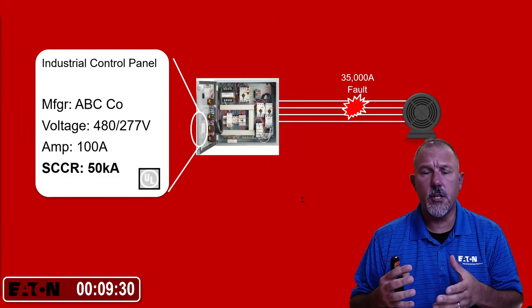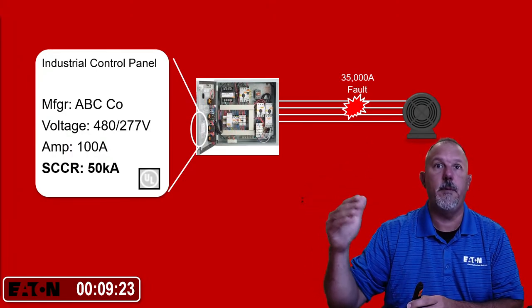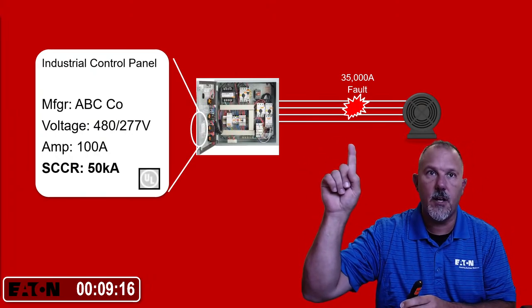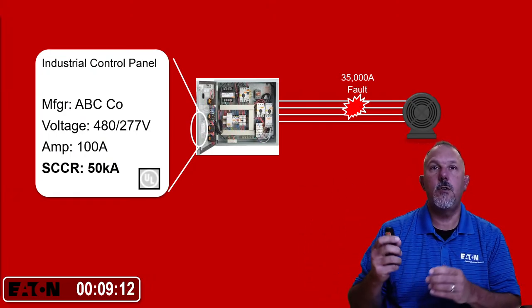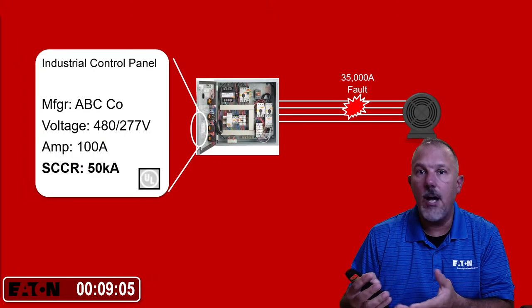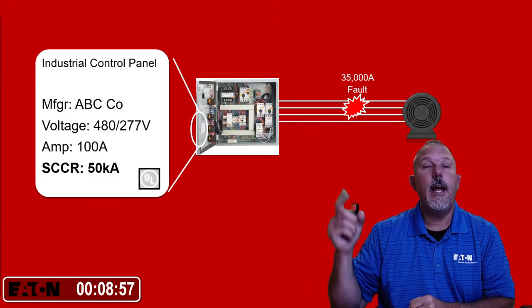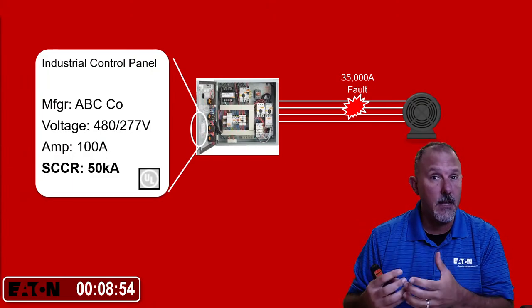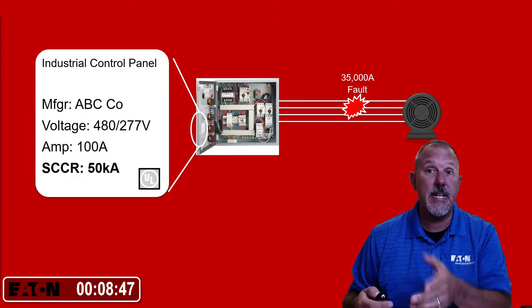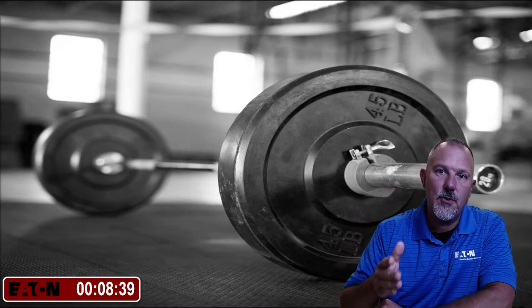Another way to explain SCCR: the fault is happening downstream of the equipment, not inside it. When an industrial control panel lets current flow through it, all the parts and pieces have to hold together. In this example, I have 35,000 amps of calculated bolted fault current RMS and a rating of 50,000 amps — I'm applying this product within its ratings.